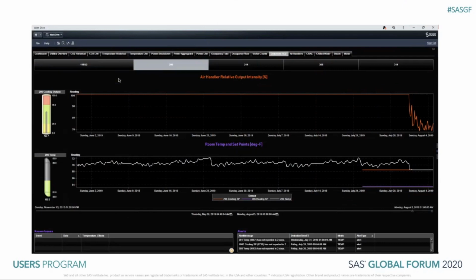We did a further investigation and found two other data rooms with the same problem. They corrected it, and you can see by this slide that instead of working at 100%, the air handler is now working at 56.7%, and the temperature is dead on. It's working really, really well.